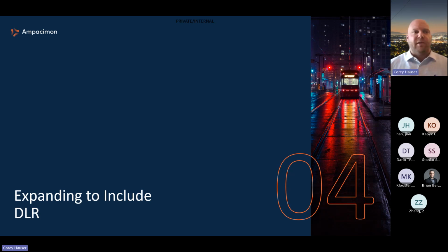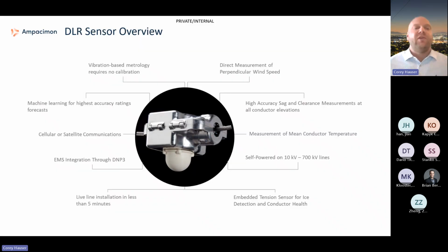Beyond just dynamic line rating, we have the ability to put tension sensors into the sensor itself, so we can measure ice accretion and galloping, expanding beyond a specific DLR use case. We have others who even use that as the more primary function of our systems. This gives you a quick rundown of our sensor: it's a vibration-based sensor, and through vibration we calculate the perpendicular wind speed, the sag, and the mean conductor temperature, providing those metrics to you in calculations and allowing them to directly drive your system's monitoring.